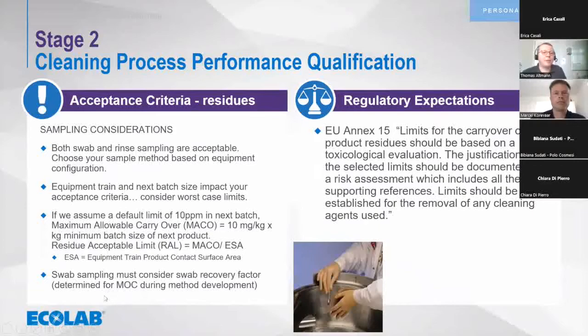And if we think that we have installed a good acceptance criteria and we have a good reading in our equipment, then it's also good to make a statement that we have a kind of process under control. And we know even if we are sampling, for example, with swabs, we have considered recovery factors. How good can I swab a surface and get the extracted residue from the surface into my analytical method so that I can find the 10 ppm. And if I only find 8 ppm, then I have 80% as a recovery factor, and that is what I calculate in with the acceptance criteria calculation.